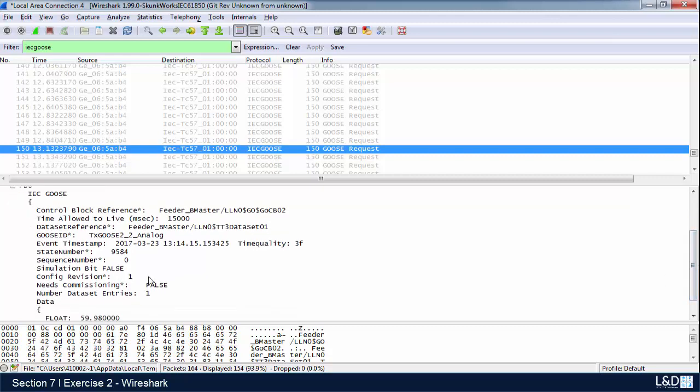The simulation bit is right now set to false. So what does this mean? Are we in test mode on the UR relays? If this is set to false, we're not in test mode. If I was to turn on the test mode and restart the analysis, this would be changed to true.